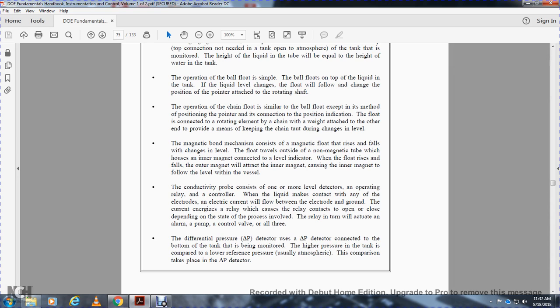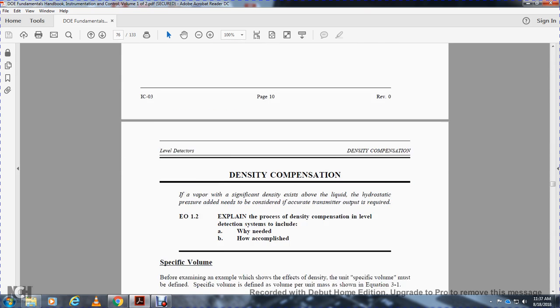Differential pressure detector. The differential pressure detector is connected to the bottom of the tank. The high pressure of the tank is compared to a low reference pressure, usually atmospheric. Typical pressure of the differential pressure detector.